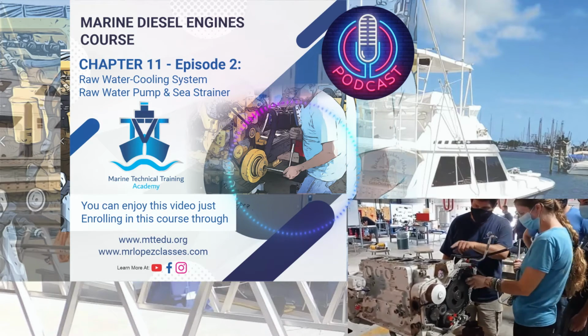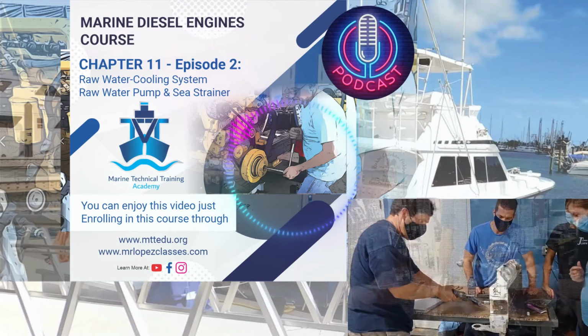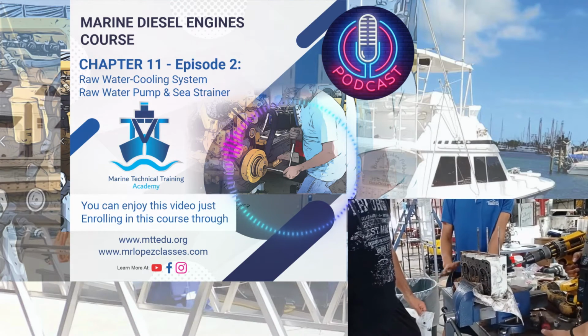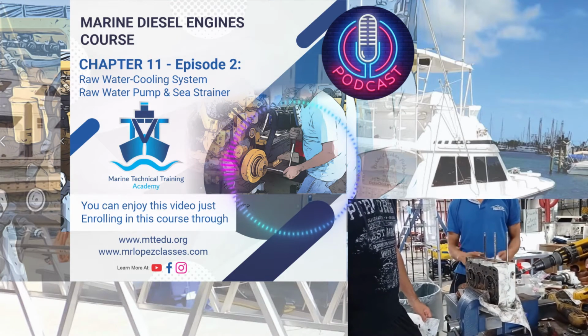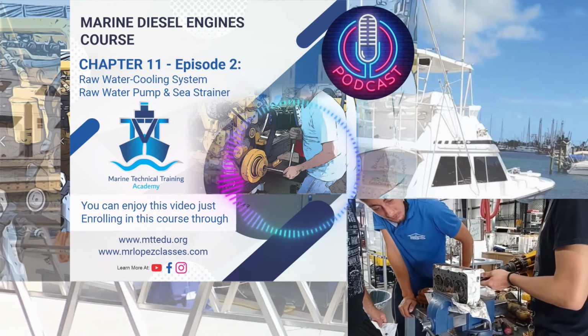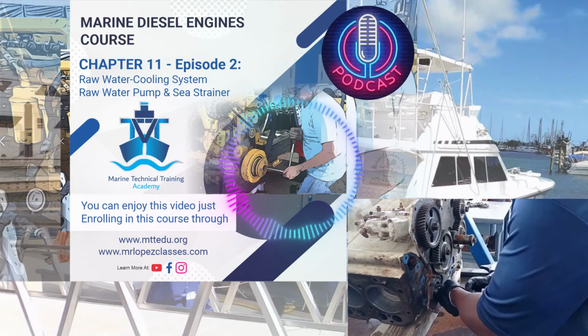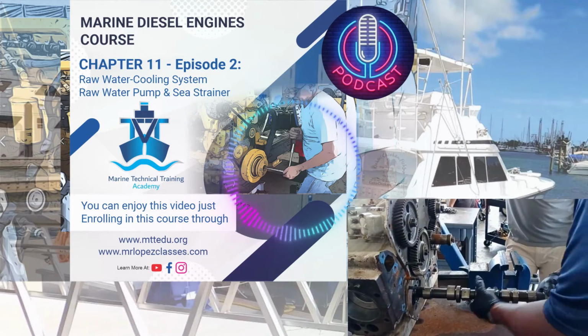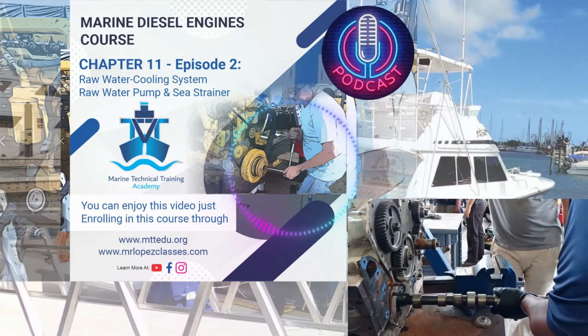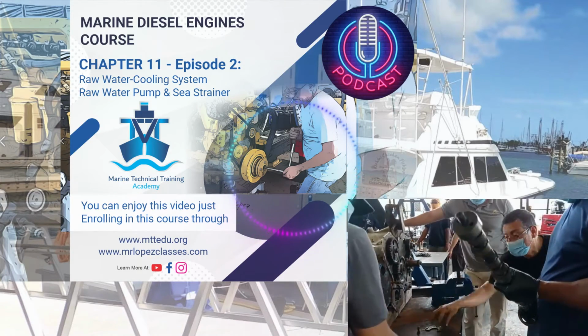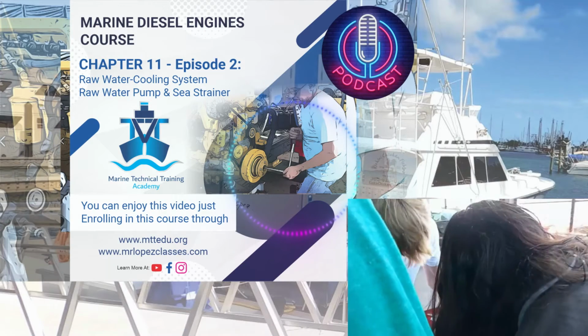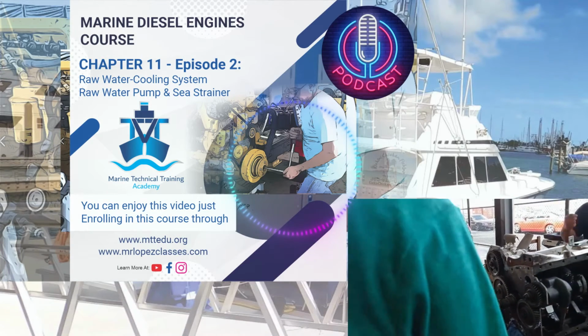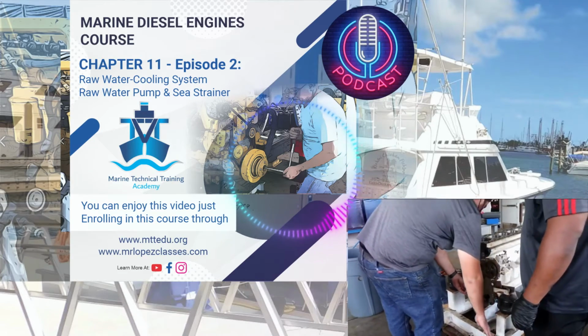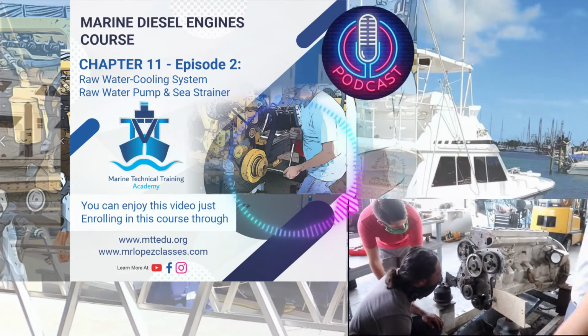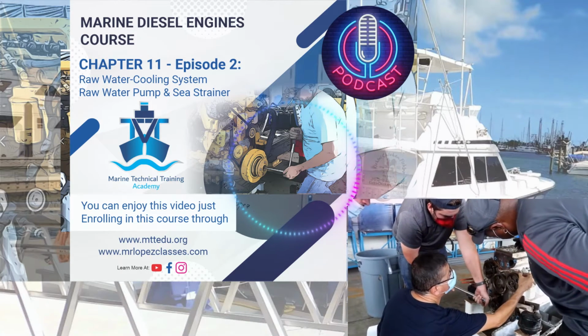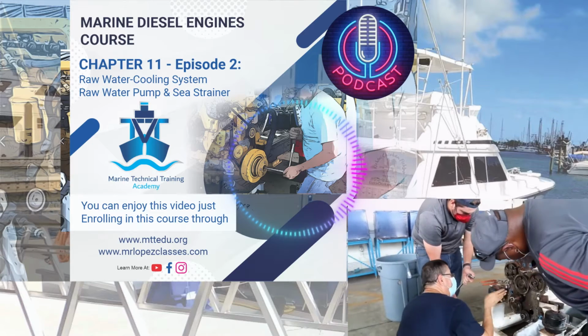Immediately you remove the plate, you have access to the impeller. As soon as you remove, you need to verify the condition of the impeller. In some cases, the blades of the impeller look in good condition, but the recommendation is bend it and verify with your fingers that they are not cracked. Bend it and verify that you don't have cracks. I recommend always replace the impeller. Or of course, if the impeller is in good condition, you can try to reuse the impeller. No, that's very important.